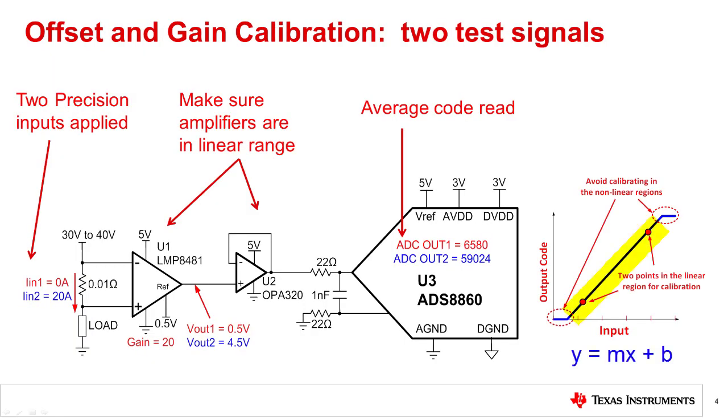The transfer characteristic for most signal chains is a linear function in the form y equals mx plus b. Technically, there will be some nonlinear terms, but assume linearity is a good first order approximation. Offset and gain calibration are based on the idea that we can solve the straight line equation for the slope and intercept. Note that the slope error is the gain error, and the intercept is the offset error. Applying two different input signals and measuring the associated output code will allow you to solve for the slope and intercept.